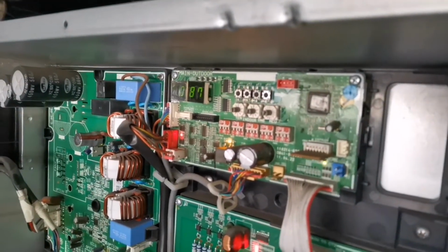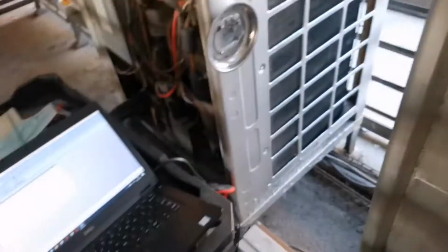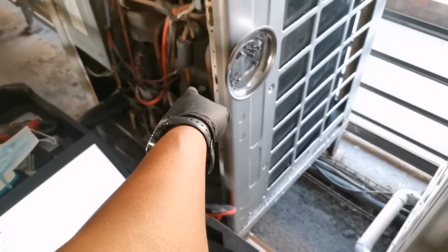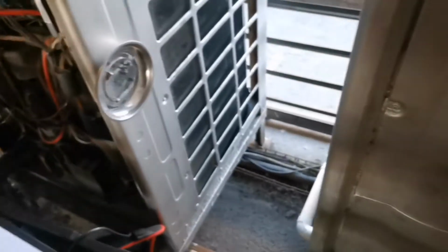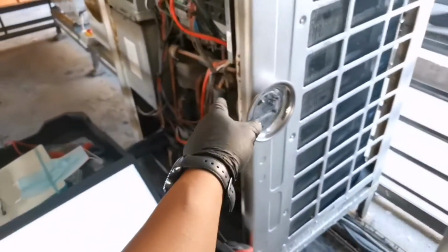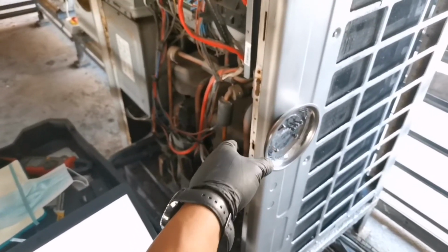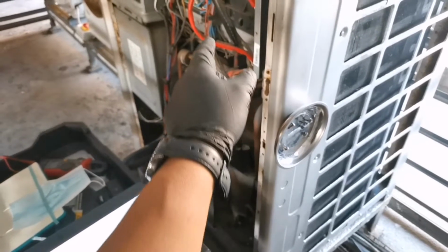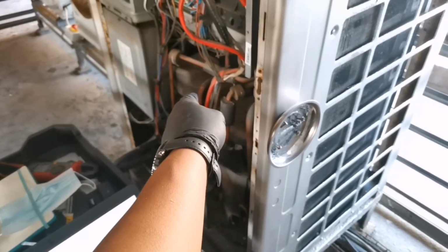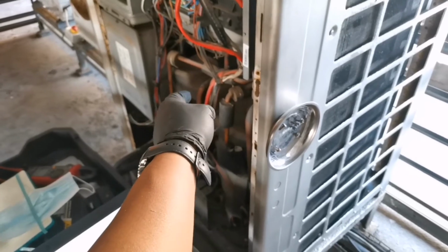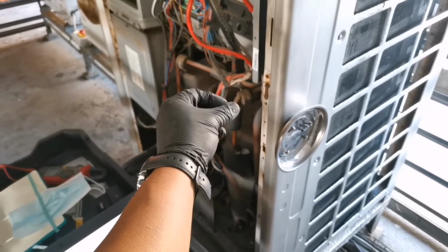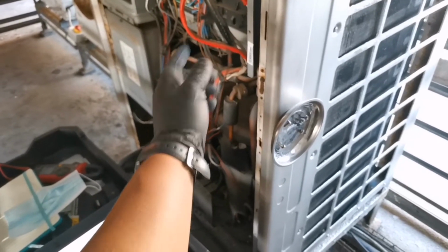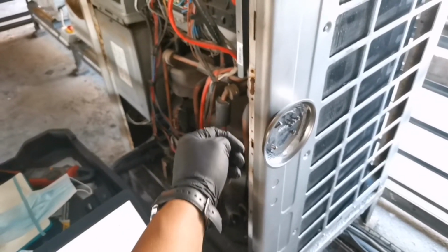As you can see, low side pressure is at 8.7 bars. So it's just running on the compressor number 2 at the moment. But obviously this unit has a sequence of events, so depending on load, it will start on compressor 1. It'll always start on compressor 1, and after about 5 minutes or so, then it will initiate compressor 2.